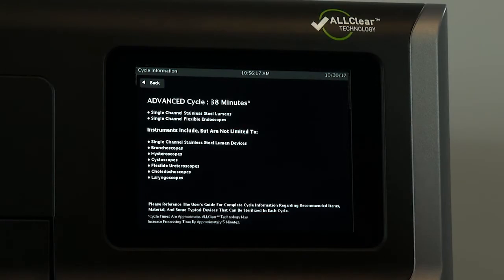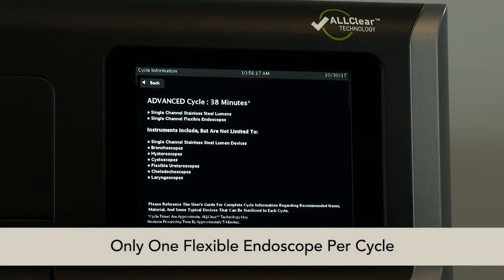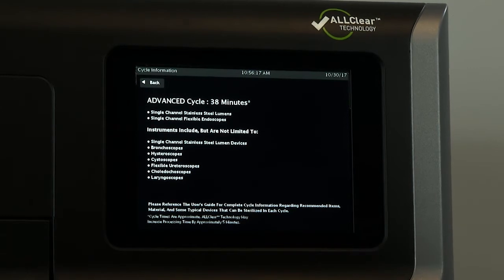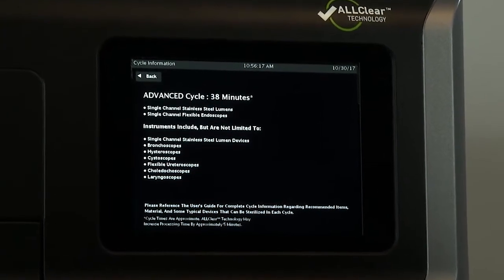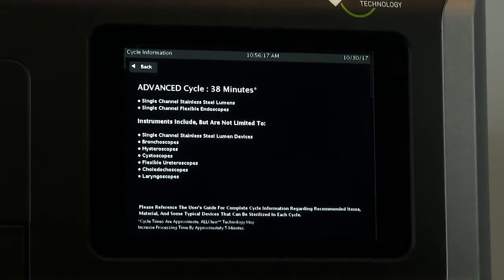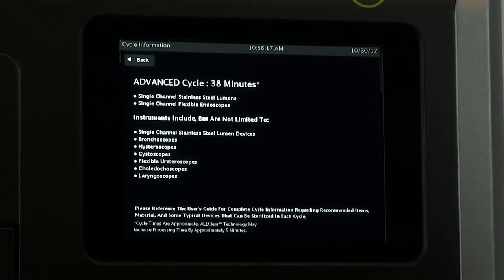The advanced cycle is 38 minutes and should be selected for single-channel stainless steel lumens with an inside diameter of 1 mm or larger and a length of 500 mm or shorter, and single-channel PE/PTFE flexible endoscopes with an inside diameter of 1 mm or larger and a length of 850 mm or shorter. Only one flexible endoscope may be sterilized per cycle with or without a silicone mat, and no additional load items may be included in that cycle. Typical single-channel flexible endoscopes would include bronchoscopes, cystoscopes, flexible ureteroscopes, choledocoscopes, and laryngoscopes.